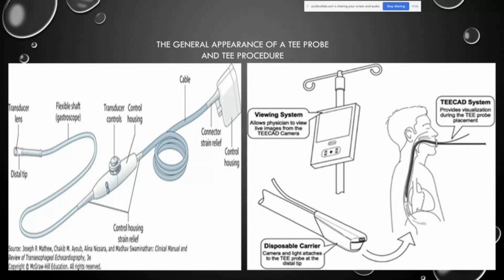And the difference between the biplane and the monoplane is that the biplane incorporates a second transducer that images in the longitudinal plane at 90 degrees. So the downside is the operator has to manually switch back and forth between the 0 plane and the 90 degrees, like manually, and that became a pain. So because of that, the multiplane probe was developed, and that probe has a single transducer that rotates within a housing at the tip of the probe, and this allows the imaging like in all planes between 0 and 180 degrees. Thank God for technology. And it also allows the transverse and longitudinal planes to be used predominantly. So big thing to remember, the multiplane or omniplane probe is the current standard for adult TEEs. It's the most commonly used one these days.